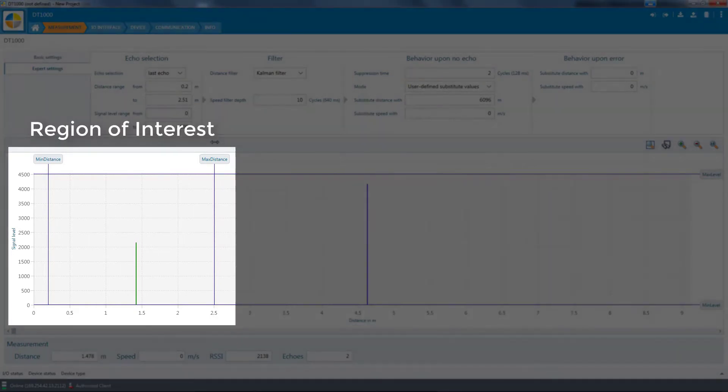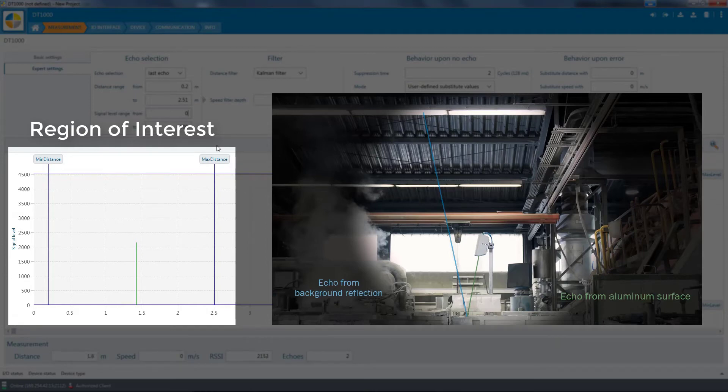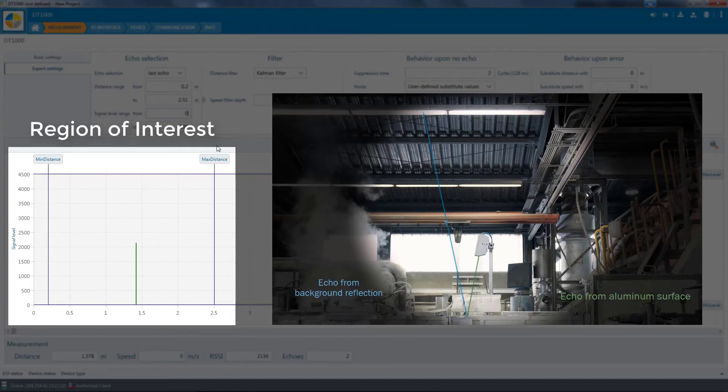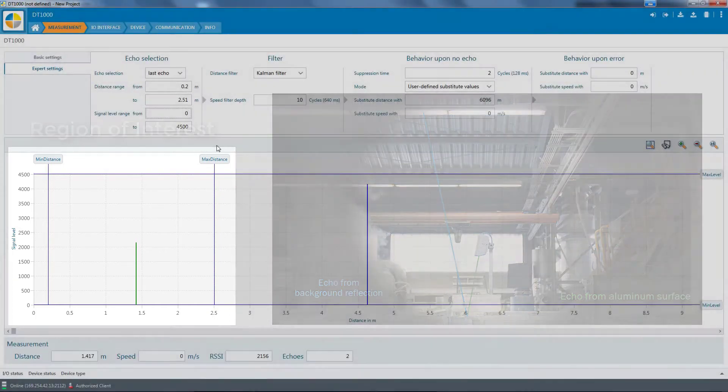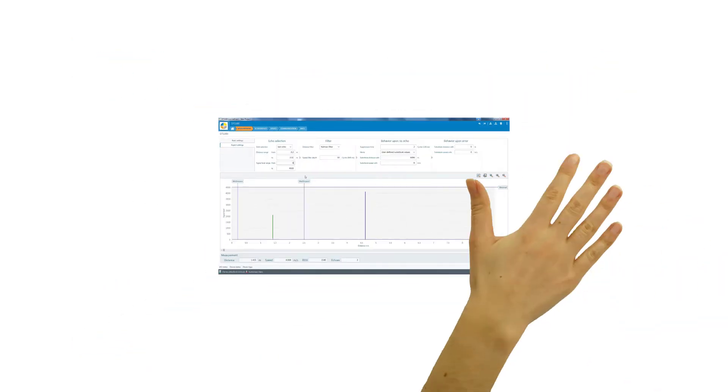The echo that originates from the background reflection provides a value that is not plausible for level measurement. We will mask it by selecting an appropriate upper distance limit. The distance sensor will therefore determine the level with a high degree of measurement certainty. This is able to take place despite the background reflection created by the mirror-like aluminum surface.